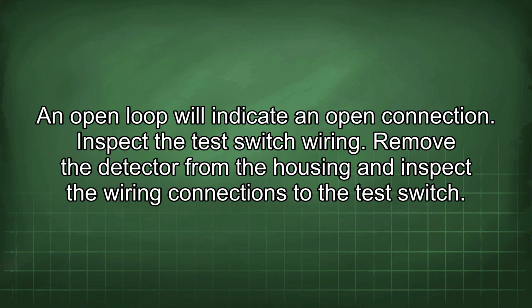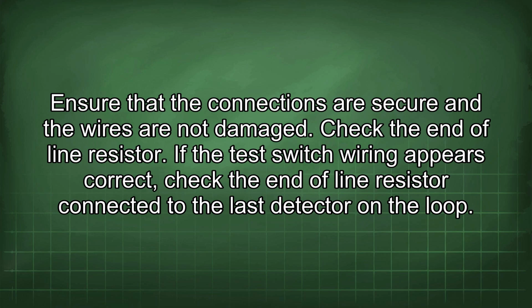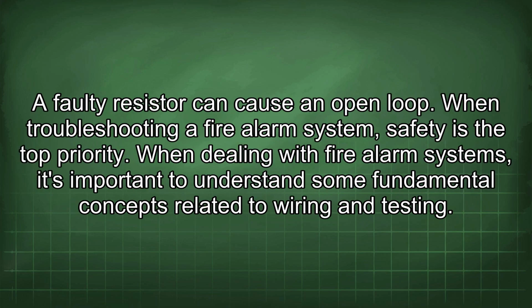Inspect the test switch wiring. Remove the detector from the housing and inspect the wiring connections to the test switch. Ensure that the connections are secure and the wires are not damaged. Check the end-of-line resistor. If the test switch wiring appears correct, check the end-of-line resistor connected to the last detector on the loop. A faulty resistor can cause an open loop. When troubleshooting a fire alarm system, safety is the top priority.